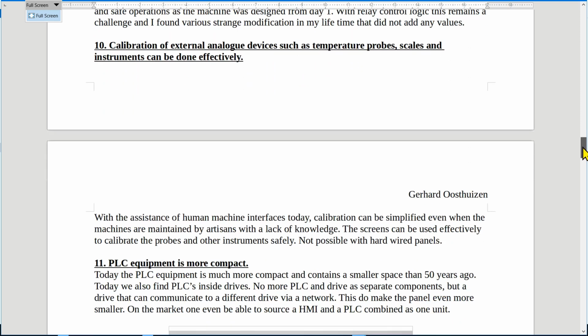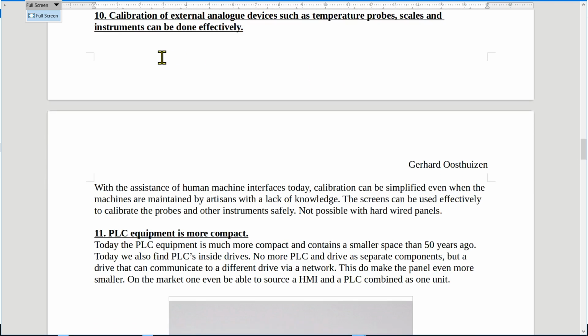Now, calibration of external analog devices such as temperature probes, scales, and instruments can be done effectively. Today we have a lot of people that are not skilled or still lack the experience because they just became an artisan. These are the people that sometimes make a mistake, not deliberately, but due to a lack of knowledge. But with the assistance of a human-machine interface today, calibrations can be simplified, even when the machines are maintained by artisans with a lack of knowledge. The screen can be used effectively to calibrate the probes and other instruments safely, which is not possible with hardwired panels.